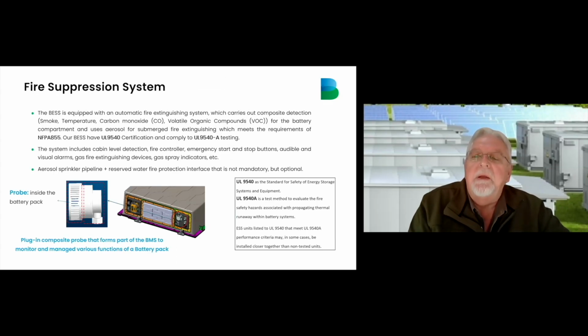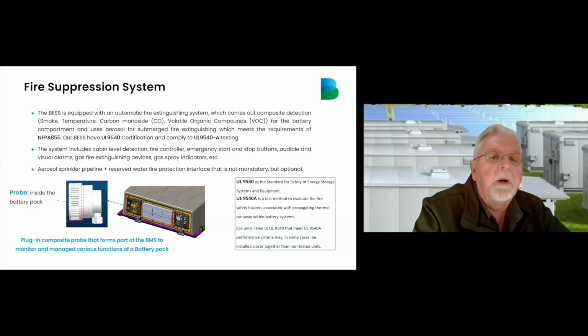A BES is equipped with an automatic fire extinguishing system to meet the requirements of the NFPA 855. The BES must comply with the UL 9540 certification and the UL 9540-A testing method. The system includes cabin level detection, fire controller, emergency start and stop buttons, audible and visual alarms, gas fire extinguishing devices, gas spray indicators, etc. The system also has aerosol sprinkler pipelines and a reserved water fire protection interface that is not mandatory but optional. The plug-in composite probe forms part of the BMS to monitor and manage various functions of your battery pack.